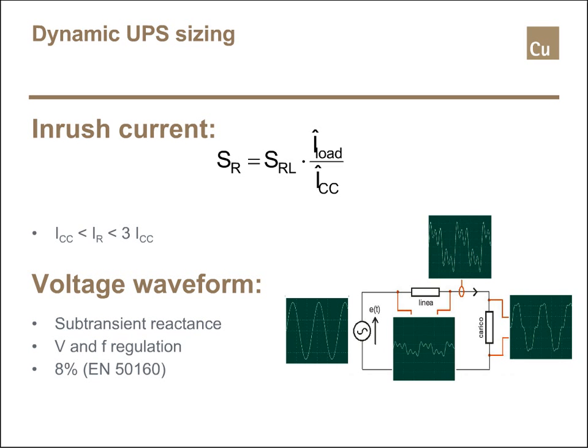Regarding how to limit voltage distortion: looking at the standards, I never found any explicit reference. My suggestion is to limit the THD to the generic allowed value in the public network in Europe — according to EN 50160, approximately 8%. If any kind of load is able to work when fed by the public network with up to 8% voltage distortion, it should work properly also with our dynamic UPS.